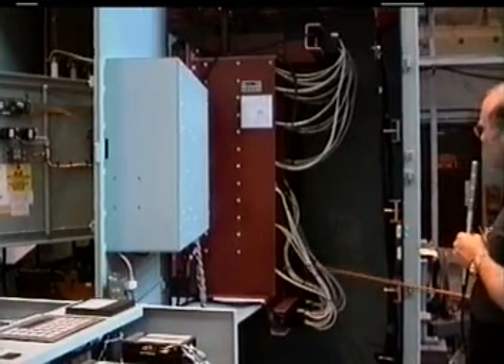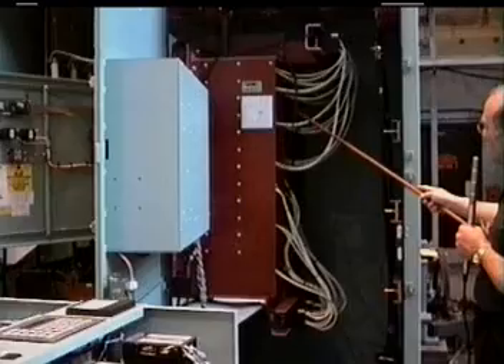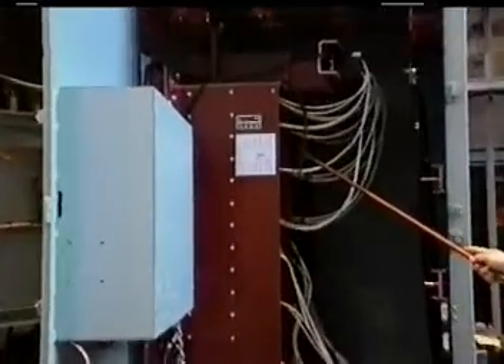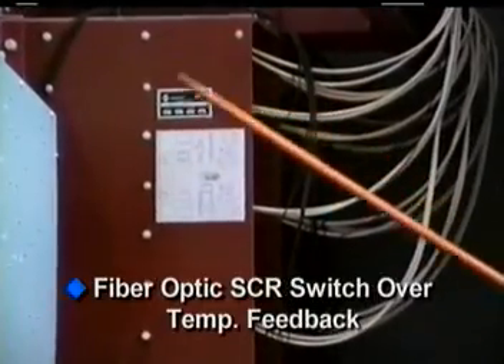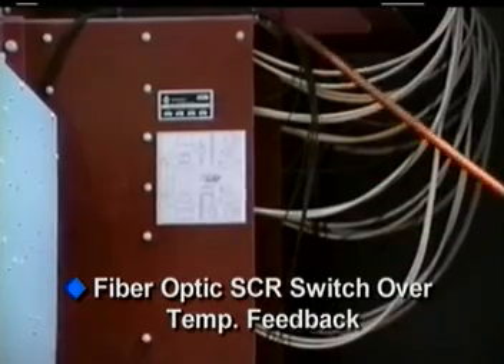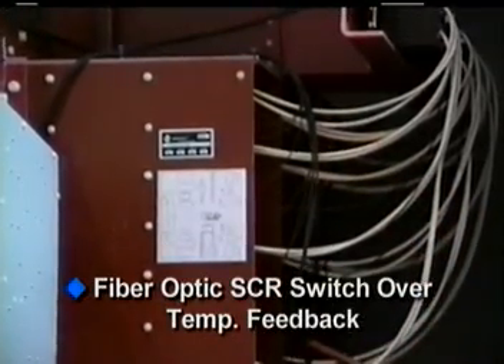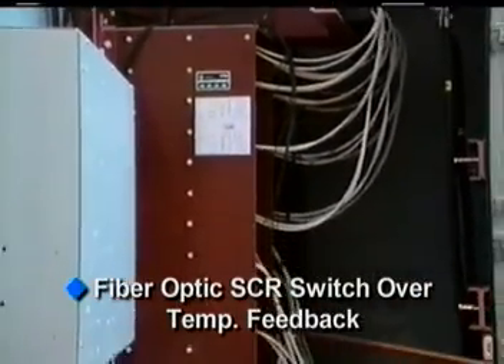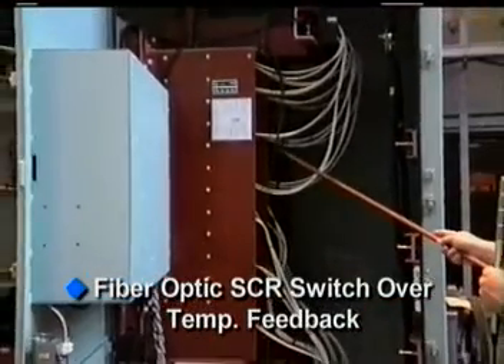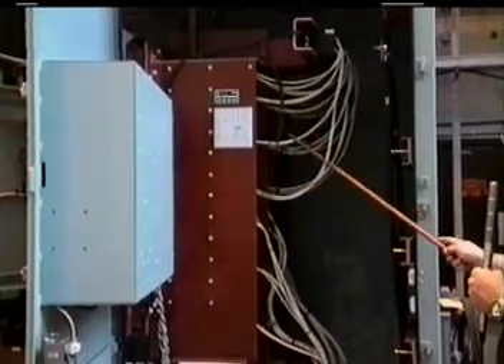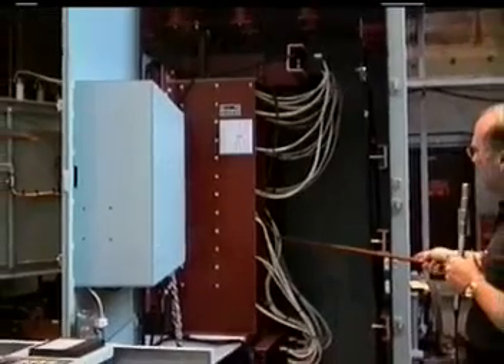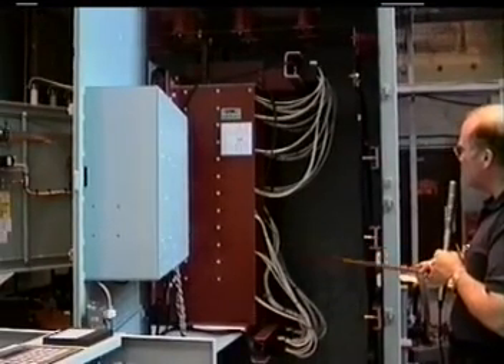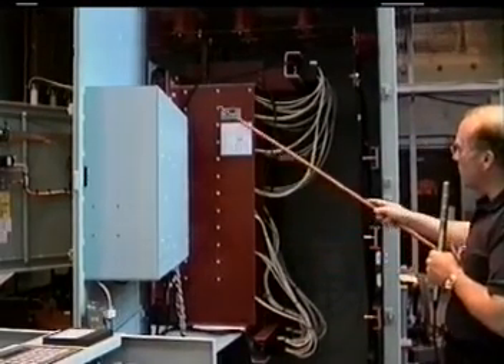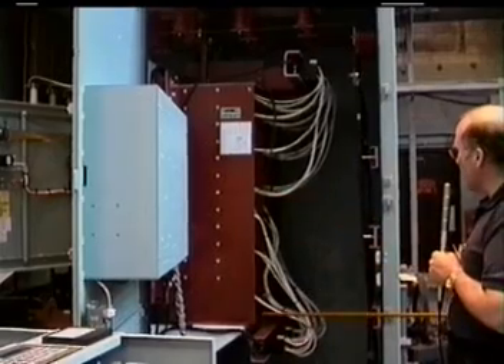The cells are fiber optically controlled by these fiber optic connections here from the low voltage section. Thus we have light pulses that are actually used to trigger the SCRs on. This provides for a very high degree of isolation between the 13.8 kV line-to-line voltage within this side of the enclosure and the low voltage compartment over here.